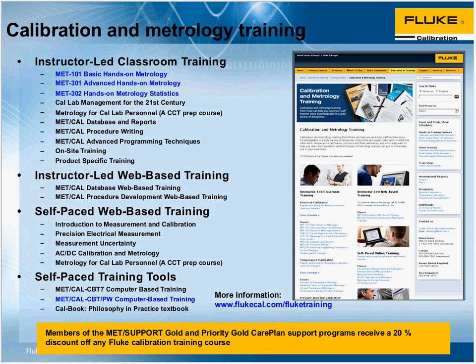And some of the units under test that get returned for calibration in the Cal lab, we might have a nice clean environment, but the users may have a somewhat less clean environment. So the instruments that get returned for calibration might be a bit grubby. We have to be careful. If that's the case, we might want to recommend that leads are cleaned, and some instruments come back looking very grubby, black and oily. That's possibly a situation where the users might need to be aware of the cleanliness issues, or we might need to give them a little cleanup. When we're calibrating the instrument, part of that is the lead, but those leads will be too dirty to make a decent measurement.